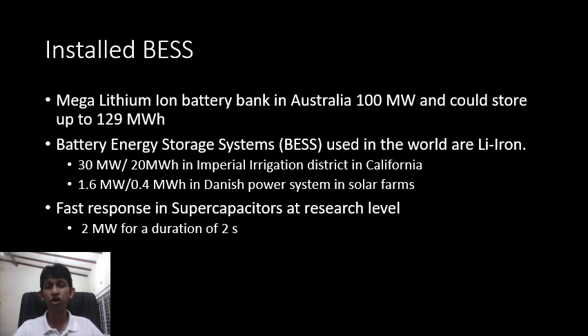By considering the inflation rate of Sri Lanka and the United States of America in 2026, if we want to have a battery energy system storage for a particular feeder, and here what we have considered is the Ratmalana 33 kV feeder number 7, that requires 2.7 billion rupees. So that is a cost aspect, which also plays a major role. So it is up to us to select which feeders need it best and which do not. And do we actually need it? Yes, we do need it in the near future, because much solar power penetration happens in day-to-day life. Day by day solar penetration occurs, and that results in drastic problems in the inertia of the system, as well as on the low voltage side.